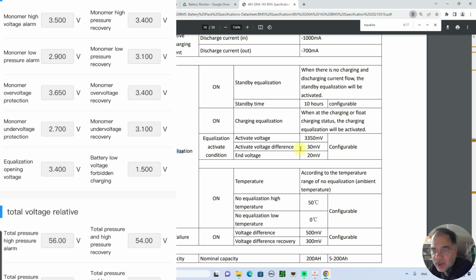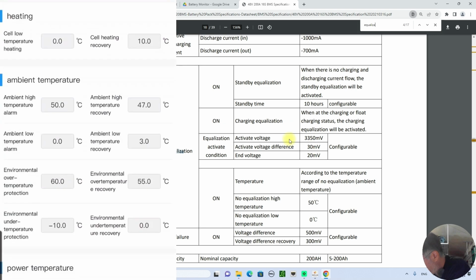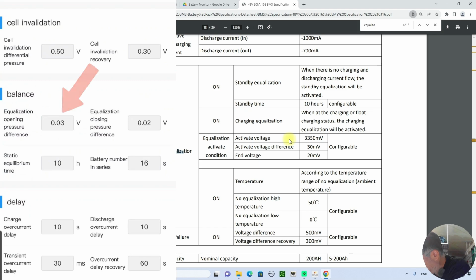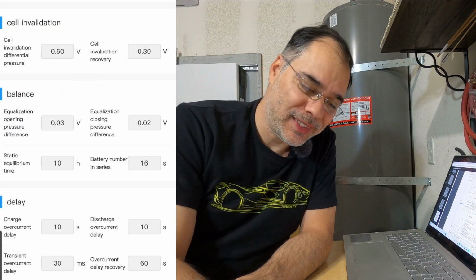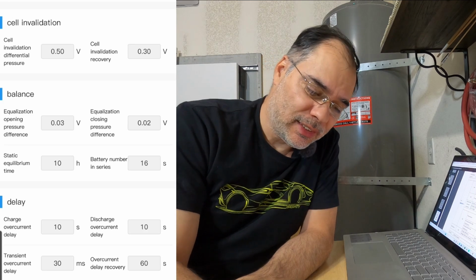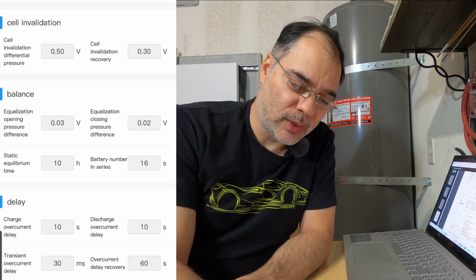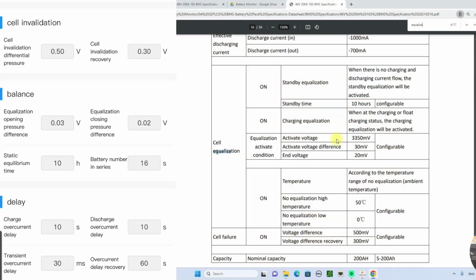And the delta has to be greater than 30 millivolts. So we'll go down here, balance equalization open pressure difference - the delta basically is 30 millivolts, that's when it starts, and it stops at 20 millivolts. So there's not a huge range there.